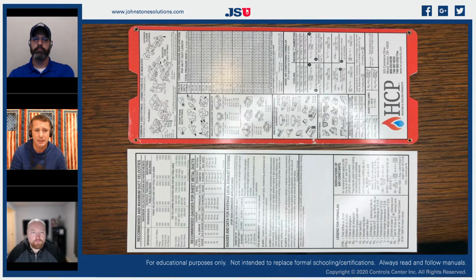He had a Victorian home that had an unfinished third floor to it, and they had already installed the equipment. They were getting ready to lay the ductwork out, and he had some concerns about the sizing of ductwork that the contractor was using. So I went over and I took my duct calculator and took my tape measure and immediately found that it was incredibly insufficient for what they were trying to accomplish.